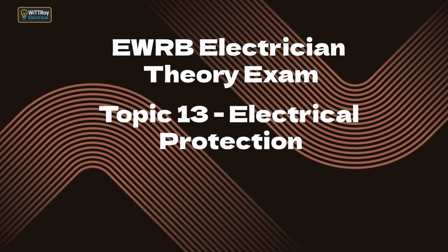13.3c Explain why it is necessary, when two or more electrical appliances are connected simultaneously to one isolating transformer, their earth continuity conductors are bonded together at the transformer but must not be earthed. If more than one appliance is connected to an isolating transformer, all exposed metal parts must be kept at the same electrical potential. To achieve this, the earth continuity conductors must be bonded together at the transformer. This ensures all appliance frames sit at the same voltage. That way, if a person touches two appliances, there is no voltage difference across their body.